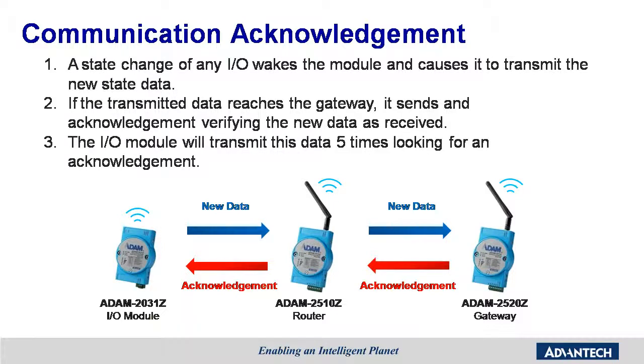When the gateway receives the data, it actually sends an acknowledgement back to the I/O module through the routers, through the repeaters, to verify that it received the correct data. If the I/O module, like the 2031Z humidity and temperature module, does not receive that ACK or acknowledgement, it will continue to send the data for an additional 5 repetitions, and it'll wait for an ACK. So that takes a finite period of time to accomplish, and that makes it very deterministic. Although this is not as fast as the determinism and predictability of something like PLC scan, it is deterministic and will complete its acknowledgement process in those 5 tries. And so it's very usable in the right applications.